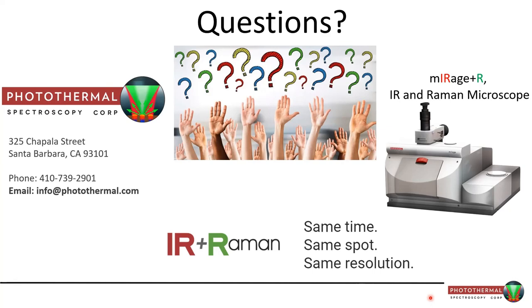Question about the fluorescence module: do you use the probe laser as the excitation for fluorescence, or additional lasers? An important clarification first: if there is fluorescence in a sample, the Raman channel will still see it, but the infrared channel is completely immune to fluorescence — even though we use a green probe for detection — because we are demodulating the modulated photothermal signal. For the wide-field fluorescence module specifically, we are not doing confocal laser scanning; we use LED excitation, though laser excitation is theoretically possible as well.